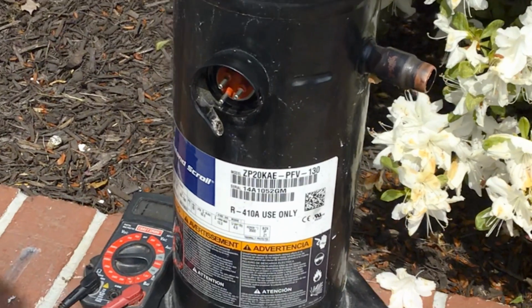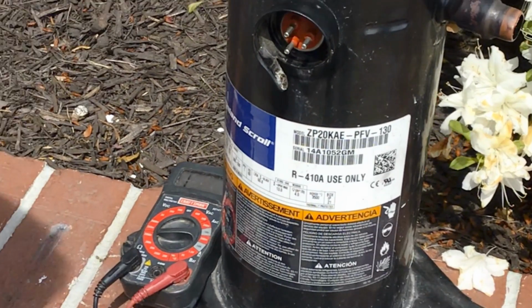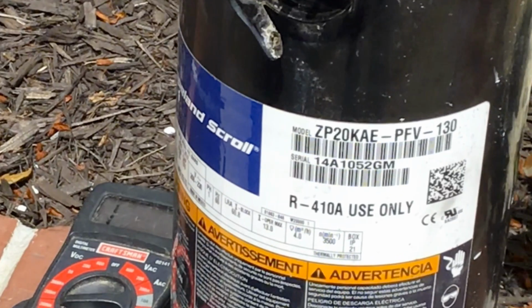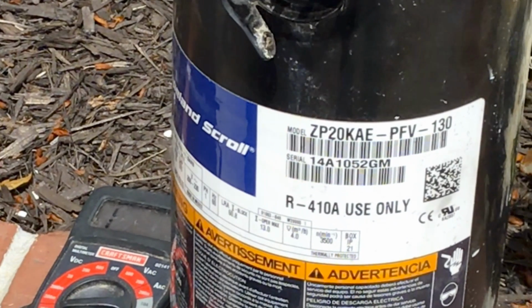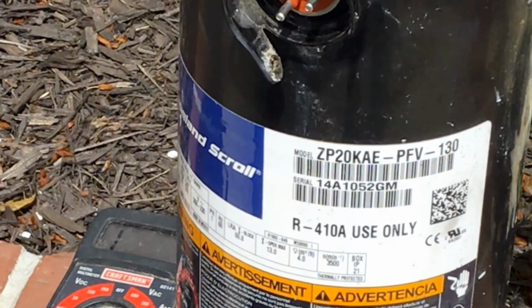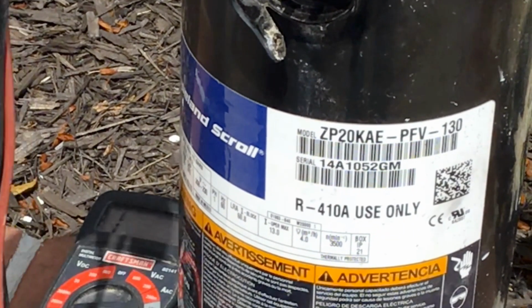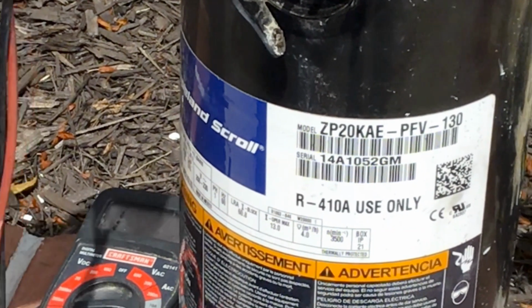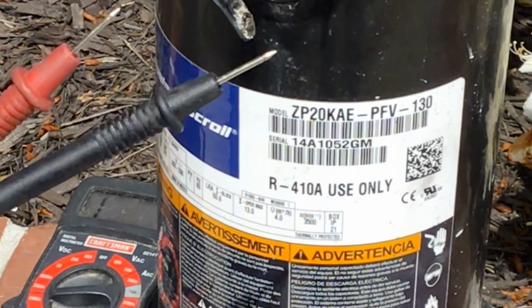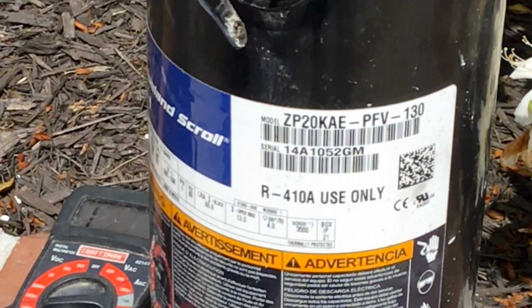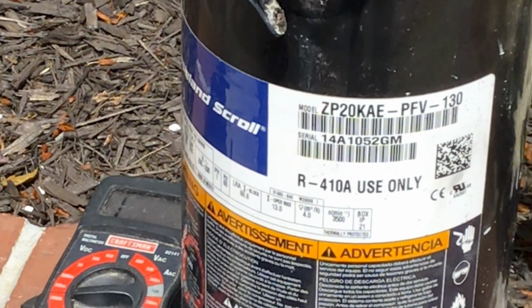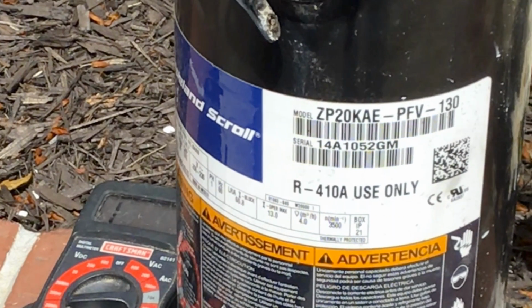All right, and the last test I'm going to show you that you can perform on a compressor to tell if it's failed or beginning to fail is to test the windings. This particular compressor we just replaced today, and unfortunately all 3 of them are burnt out, so we're not going to get an accurate reading, but you can still take something from it.